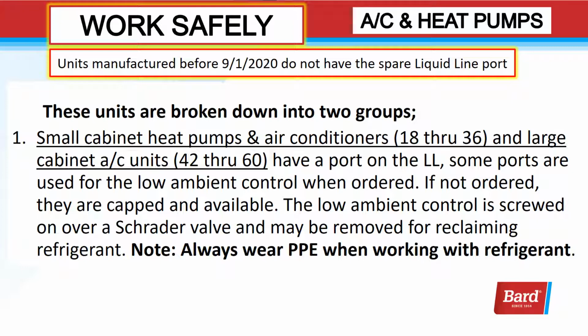Those units all have a port on the liquid line. Some ports are used for the low ambient control when that option is ordered. If the option is not ordered, they're just capped and they're available. So the low ambient control is screwed on over a Schrader valve and may be removed for reclaiming refrigerant. And always wear your proper PPE when working with refrigerant.